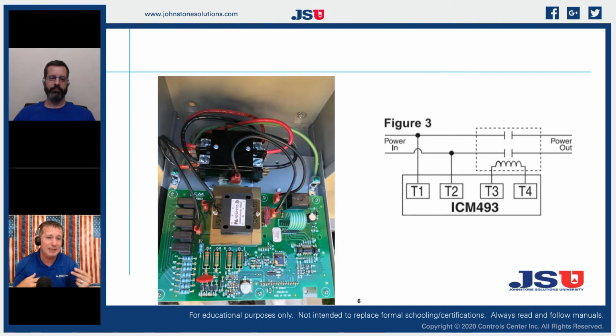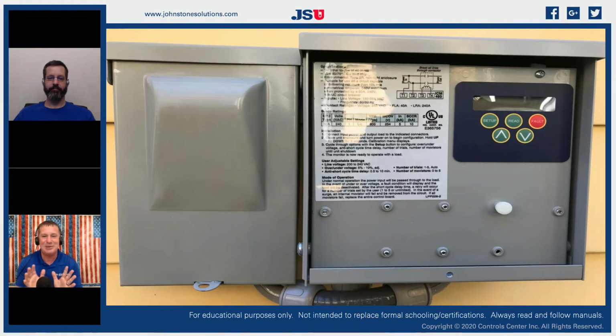So you have power coming in that is feeding to the control system. You got power that's feeding out off from our contactor. And so now we can condition the voltage with our board, and then we can drop out the component completely. So that's good to know, Paul, that we're seeing those, because that's exactly what I use on my inverter systems. So this is one system that I did in the field for one of our contractors. This was a multi-head, a multi-split system that they were having control board failure issues with, and they didn't have control board failure issues with this particular piece of equipment until a new building was constructed just down the road, just about a half a block. And when they did, they put an entire new circuit of transformers. And so they were having very irregular voltage spikes off from the system and just literally smoking the boards on this thing. So we added in a ICM 493 to monitor that voltage, and haven't heard from them in a year.